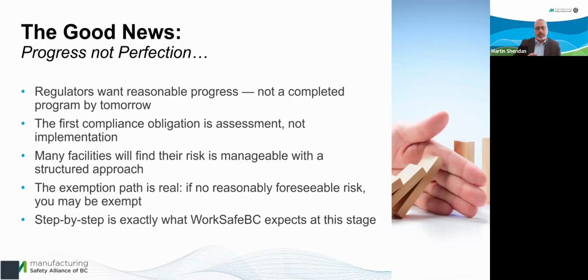A combustible dust assessment can help figure that out. There is an exemption path, and it's real: if you have no reasonably foreseeable risk, you may be exempt. It's in your best interest to figure that out, and we'll talk about how in a couple of slides. So step by step is what WorkSafeBC is looking for at this stage: first, do these regulations apply, and is there a foreseeable risk or not?